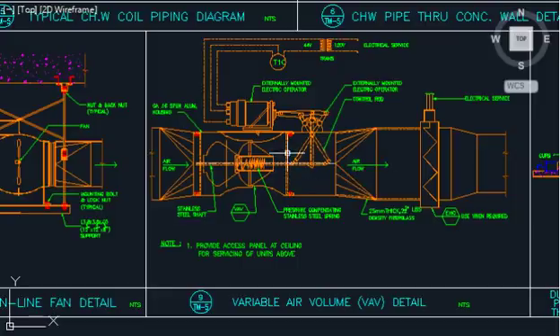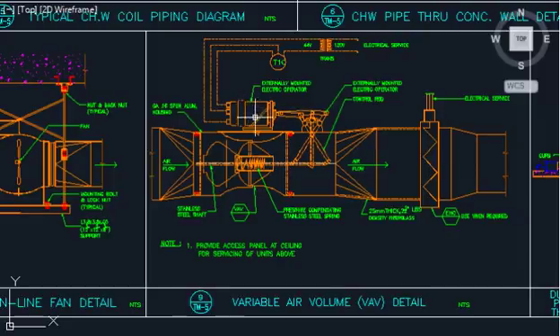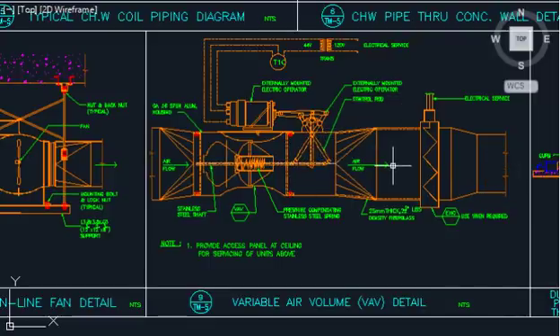With the help of VAV, we can reduce the temperature in the room because the air is coming directly serving multiple rooms and areas. There is a motorized damper here controlled by the VAV. We need 600 CFM, so 1200 is coming in and they will shut it down 50%, delivering 600 CFM to this room.